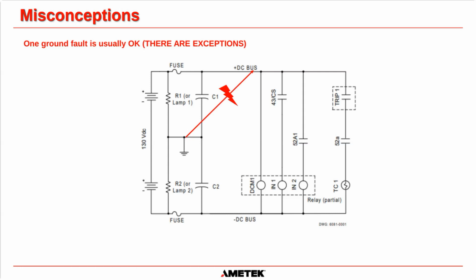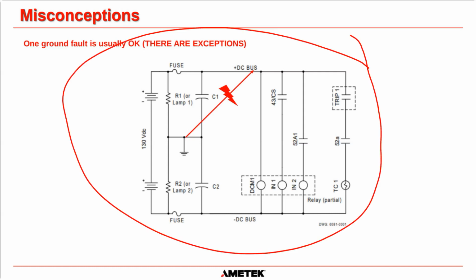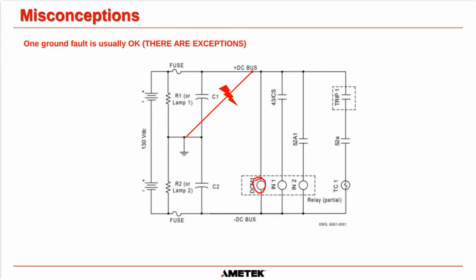But this circuit here is basically a cut-down version of a switchgear control circuit, okay? You've got your coils down here, you've got your contacts here, and there's whatever your motor or whatever you're sending a signal to out there, okay? So basically, we have our battery connected to the switchgear system. It says 130 volts DC there. This is our ground fault detection circuit.